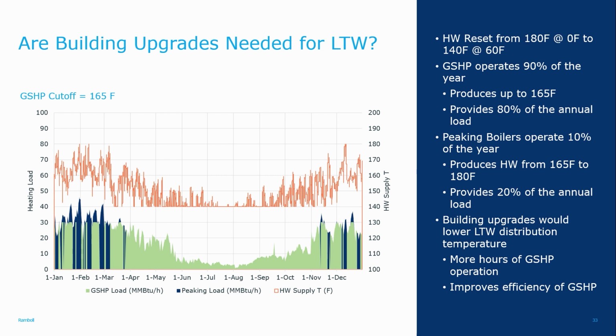With a reset schedule, producing 180 during colder periods and dropping down to 140, we can set when the heat pumps will operate. We put a cutoff at 165 degrees, which you saw in some earlier examples, where the heat pumps are producing 165. So they'll operate up to 165, then shut off, and the peaking boilers take over for anything above 165 that's needed.